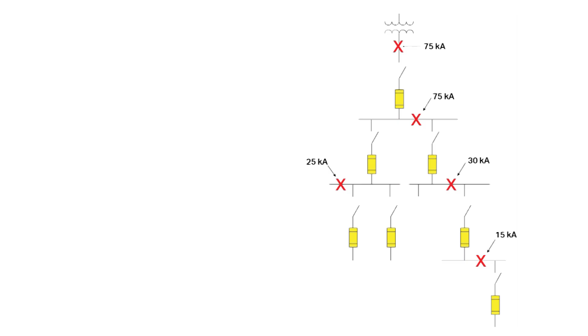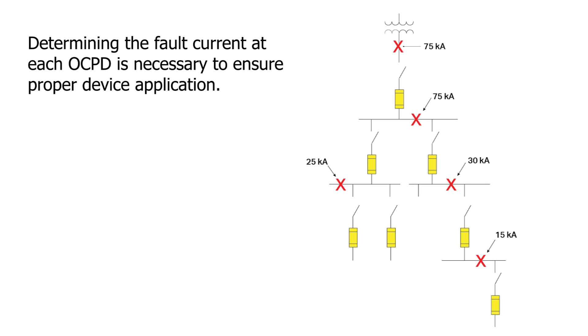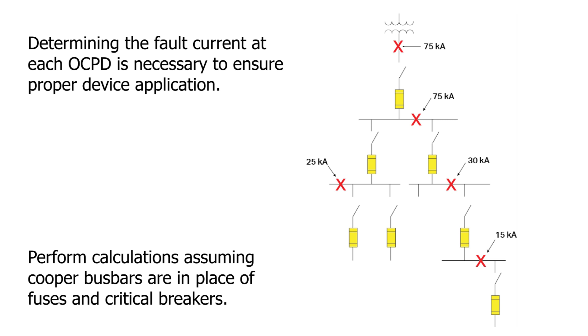It is important to note that short circuit calculations in a system are performed without any overcurrent protective devices, such as fuses or circuit breakers, in the system. Calculations are completed assuming copper bus bars are replacing these devices to determine the maximum available fault current at various points in the system. Only then should the effect of the protective device be analyzed.